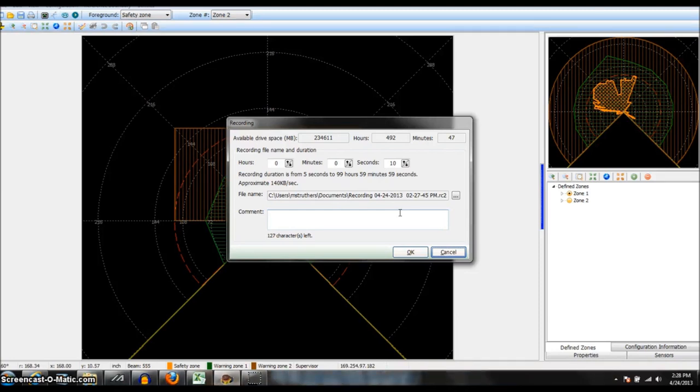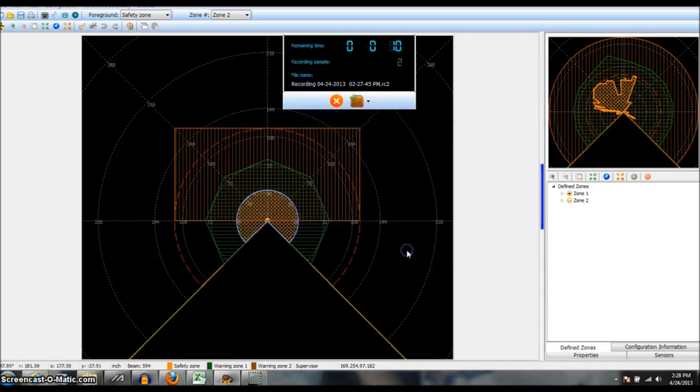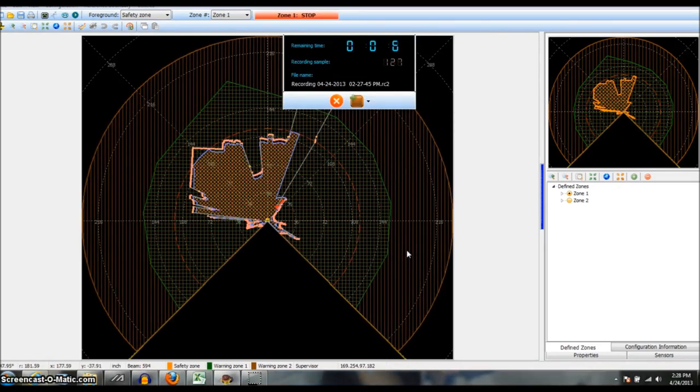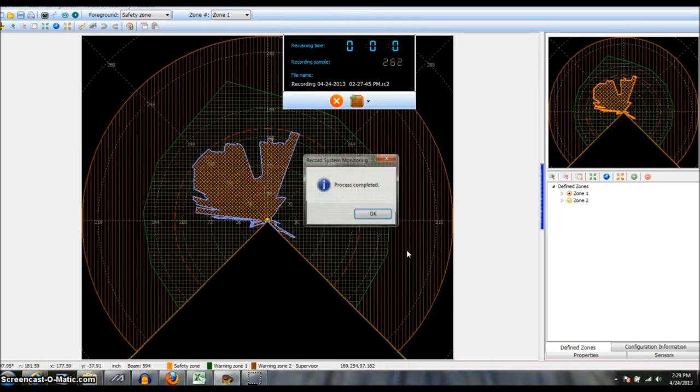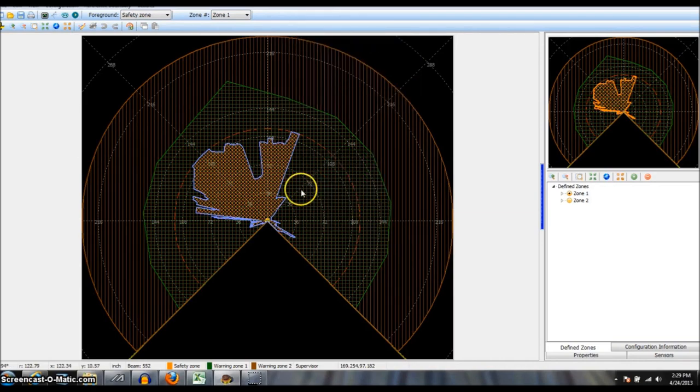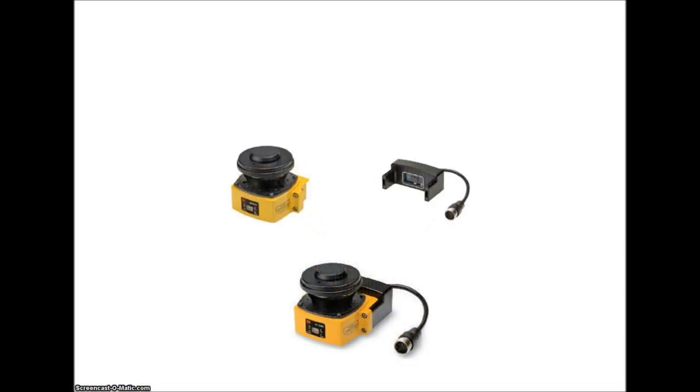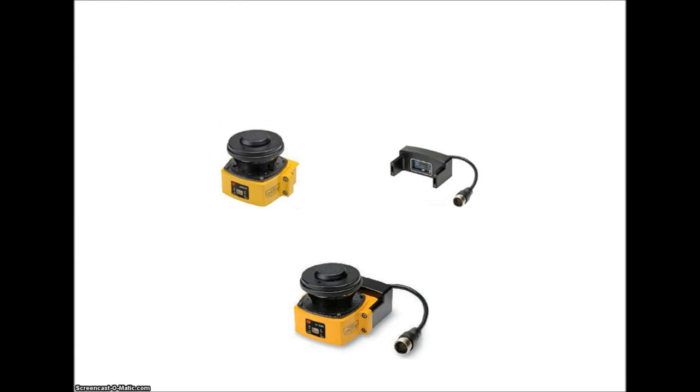Now we need to be able to monitor this so that we can configure the zones accordingly. And the recording option is a great way to do that. So right now it's recording. I'll go ahead and move my hand around. And the pre-specified time is complete. The memory block is quick disconnect. So if you need to replace the scanner you can take off the memory block and reattach the new scanner. No further configuration or programming is required.